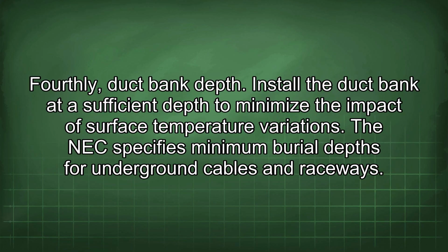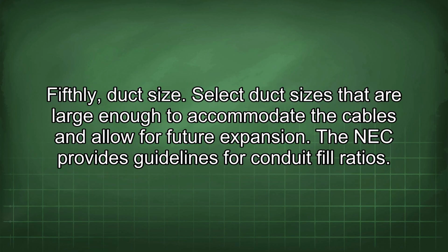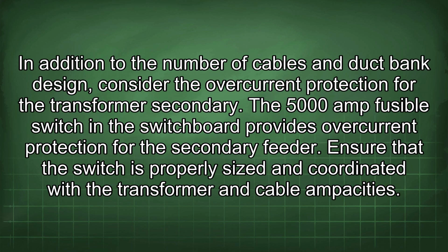Fourthly, duct bank depth. Install the duct bank at a sufficient depth to minimize the impact of surface temperature variations. The NEC specifies minimum burial depths for underground cables and raceways. Fifthly, duct size. Select duct sizes that are large enough to accommodate the cables and allow for future expansion. The NEC provides guidelines for conduit fill ratios. In addition to the number of cables and duct bank design, consider the overcurrent protection for the transformer secondary.